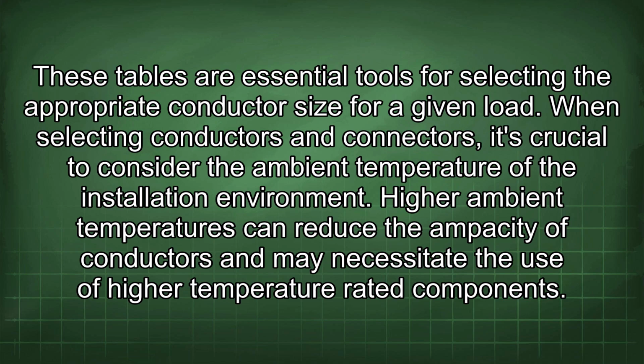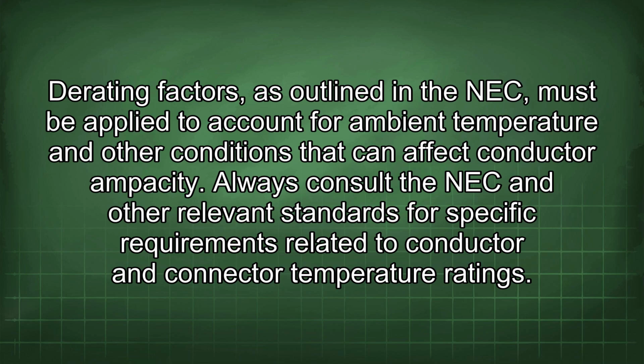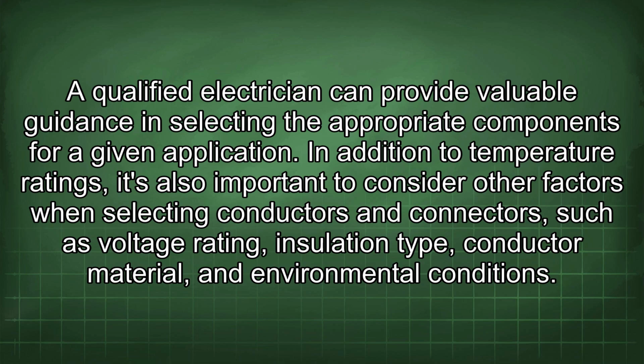When selecting conductors and connectors, it's crucial to consider the ambient temperature of the installation environment. Higher ambient temperatures can reduce the ampacity of conductors and may necessitate the use of higher temperature rated components. Derating factors, as outlined in the NEC, must be applied to account for ambient temperature and other conditions that can affect conductor ampacity. Always consult the NEC and other relevant standards for specific requirements related to conductor and connector temperature ratings. A qualified electrician can provide valuable guidance in selecting the appropriate components for a given application.